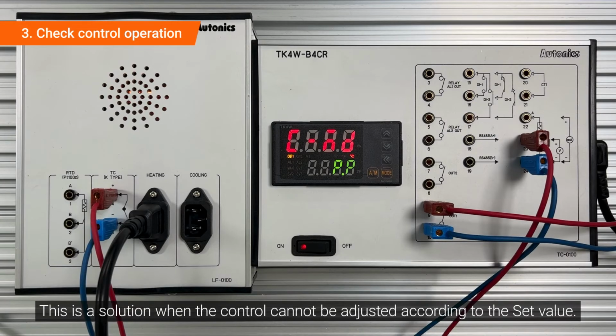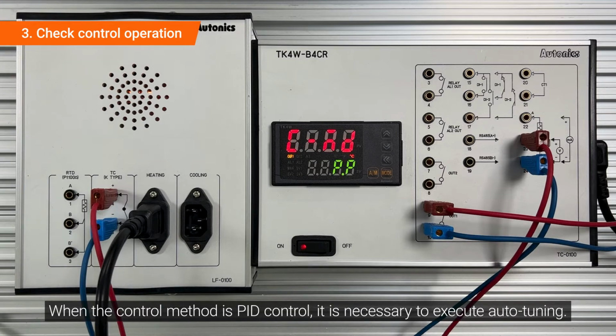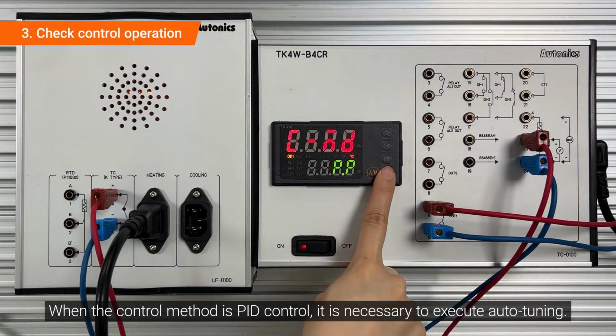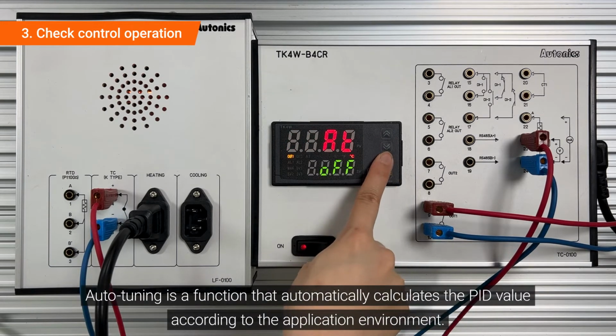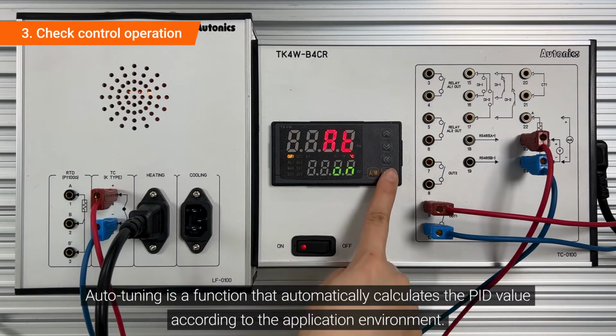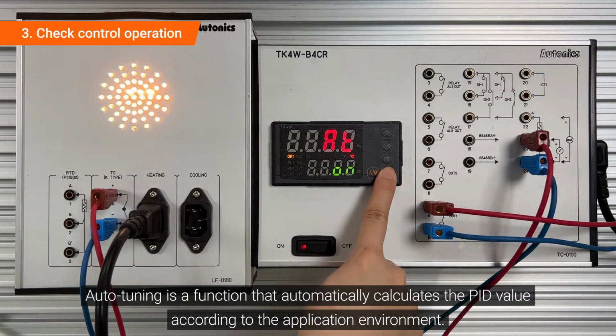This is a solution when the control cannot be adjusted according to the set value. When the control method is PID control, it is necessary to execute auto-tuning. Auto-tuning is a function that automatically calculates the PID value according to the application environment.